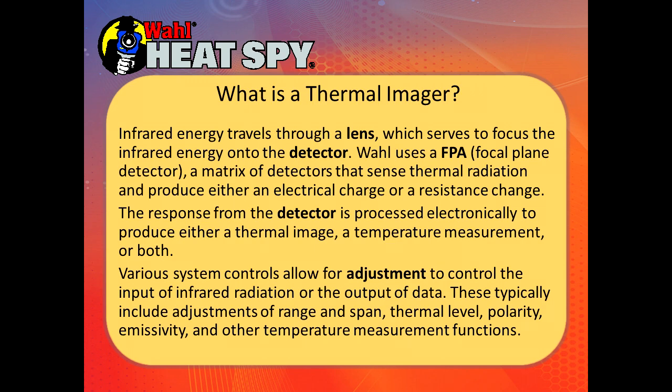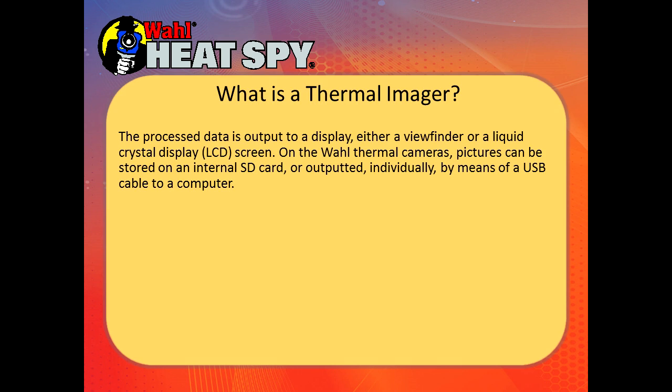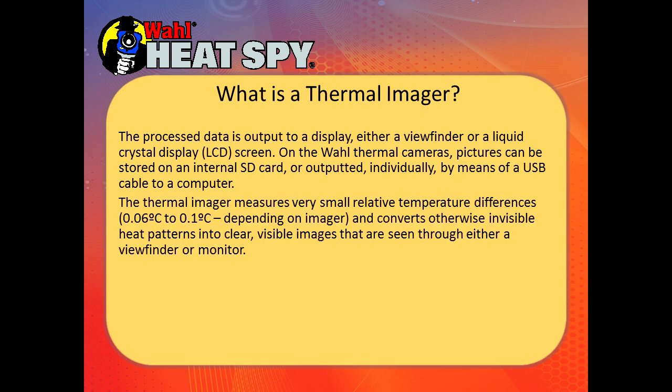The response from the detector is processed electronically to produce a thermal image, a temperature measurement, or both. Various control systems allow adjustment of range, span, thermal level, polarity, emissivity, and other temperature measurement functions. Processed data is output to a display screen — either viewfinder or liquid crystal screen. On Wahl thermal cameras, pictures can be stored on an internal SD card or output via a USB cable to a computer. Thermal imagery measures very small temperature differences — our imagers measure from 0.06°C to 0.1°C depending on the model — and converts invisible heat patterns into clear visible images.